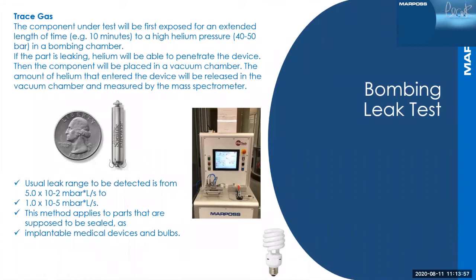One of the next trace gas methods is what we refer to as a bombing leak test. In the bombing leak test, we put the part into a chamber and pressurize the part in the chamber with helium. What we're trying to do is force helium molecules into that small part. After it's been pressurized for a while, we pull it out and put it into a special vacuum chamber and run a mass spec leak test. At that point, we're trying to pull the helium that we forced into the part back out of the part. So if there's a leak, we'll be able to detect it. This is referred to as the bombing method.